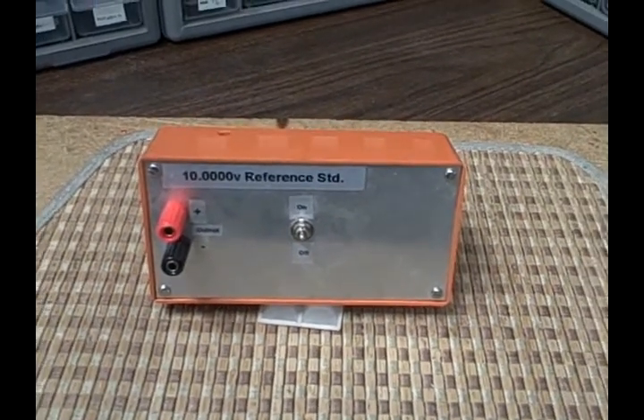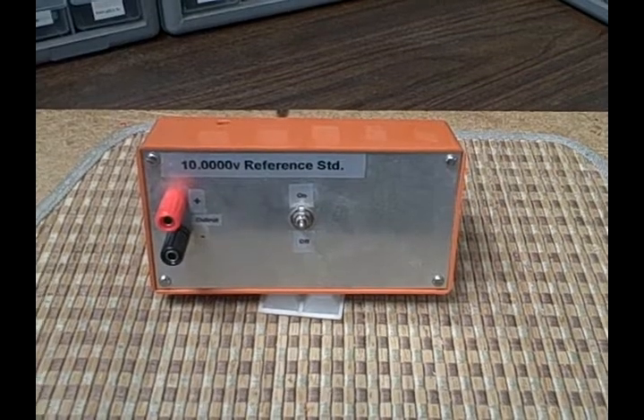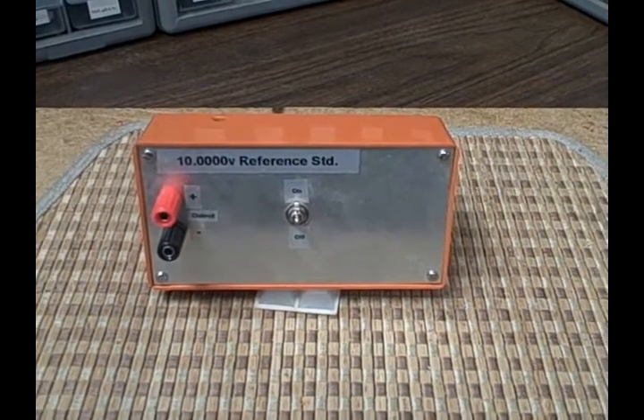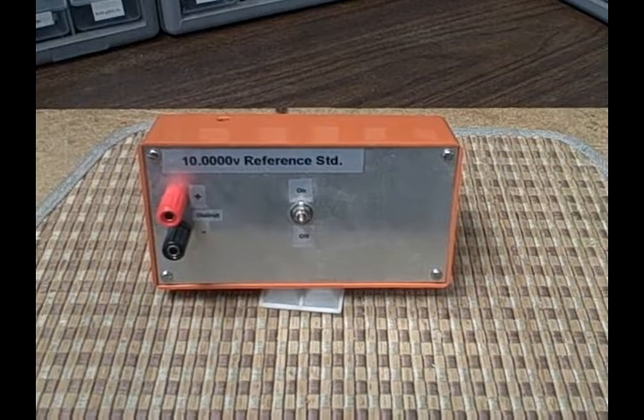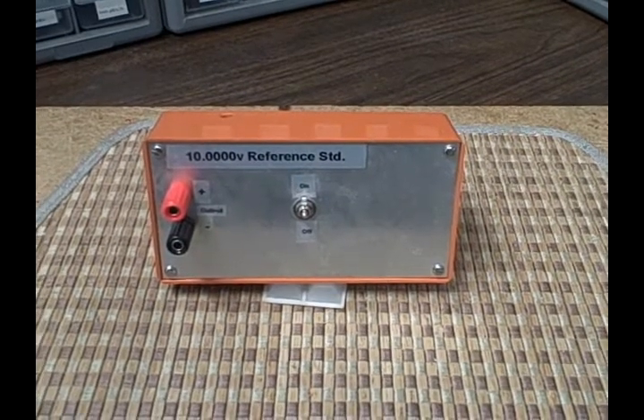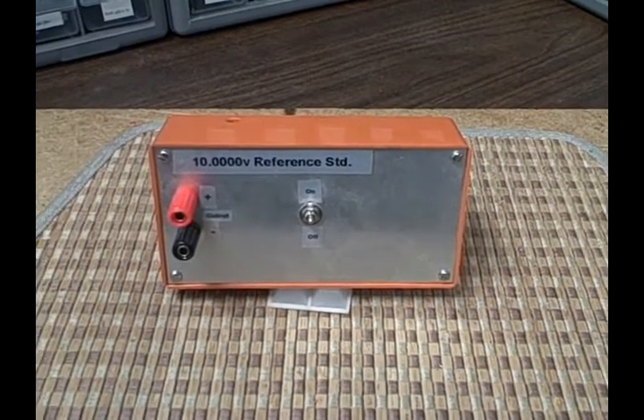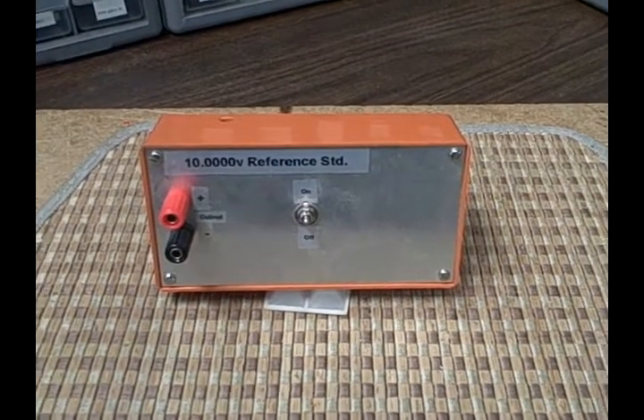I'd say that this thing, once calibrated, will hold its calibration generally for about a day in the hundred microvolt area. It may start to drift a little bit, but it'll maintain the millivolts for a matter of maybe a week.